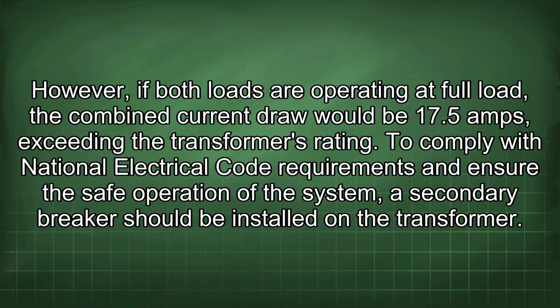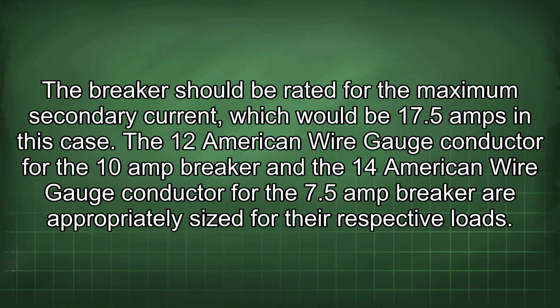rating. To comply with National Electrical Code requirements and ensure the safe operation of the system, a secondary breaker should be installed in the transformer. The breaker should be rated for the maximum secondary current, which would be 17.5 amps in this case. The 12 American wire gauge conductor for the 10 amp breaker and the 14 American wire gauge conductor for the 7.5 amp breaker are appropriately sized for their respective loads.